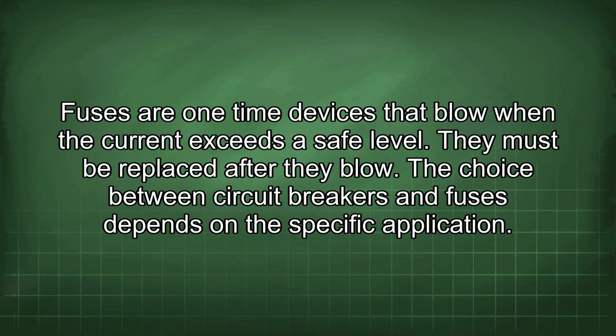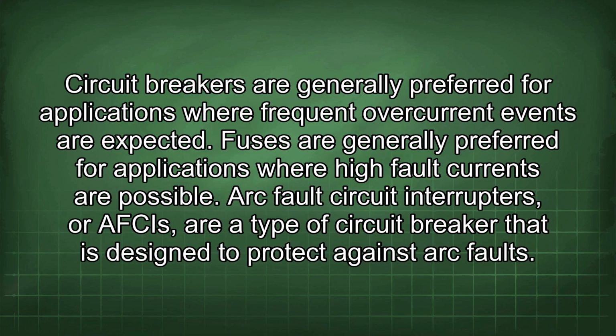The choice between circuit breakers and fuses depends on the specific application. Circuit breakers are generally preferred for applications where frequent overcurrent events are expected. Fuses are generally preferred for applications where high fault currents are possible. Arc fault circuit interrupters, or AFCIs, are a type of circuit breaker that is designed to protect against arc faults.